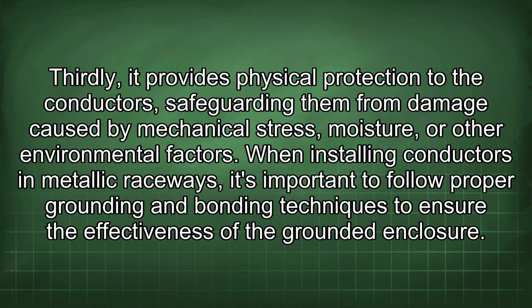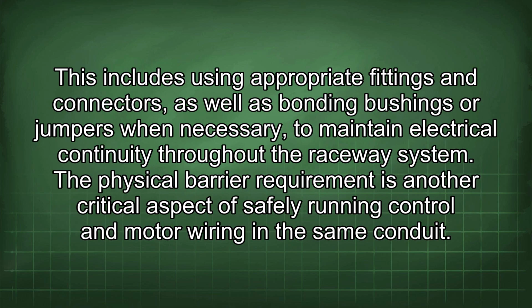When installing conductors in metallic raceways, it's important to follow proper grounding and bonding techniques to ensure the effectiveness of the grounded enclosure. This includes using appropriate fittings and connectors, as well as bonding bushings or jumpers when necessary, to maintain electrical continuity throughout the raceway system.